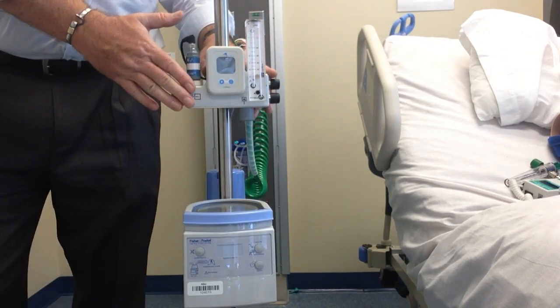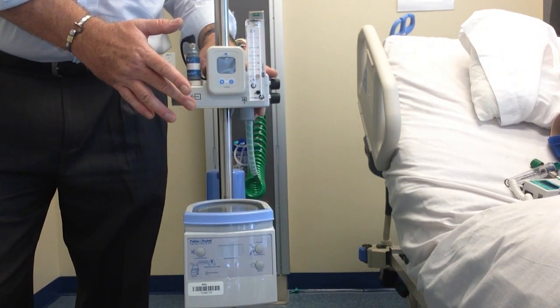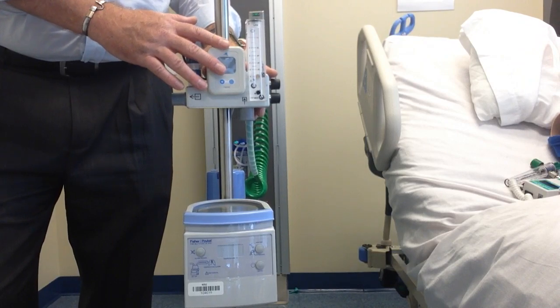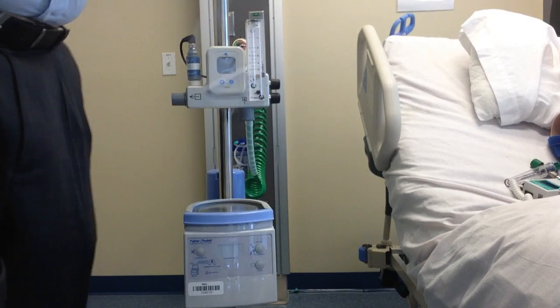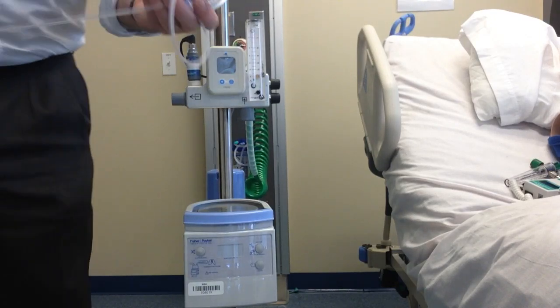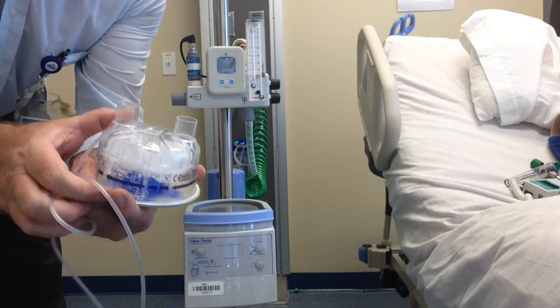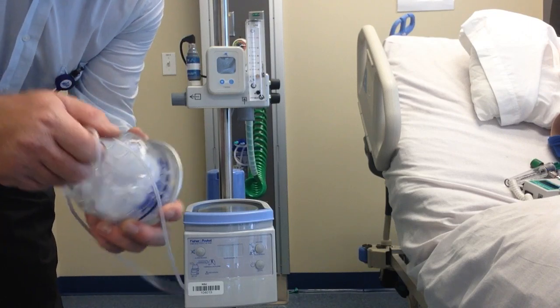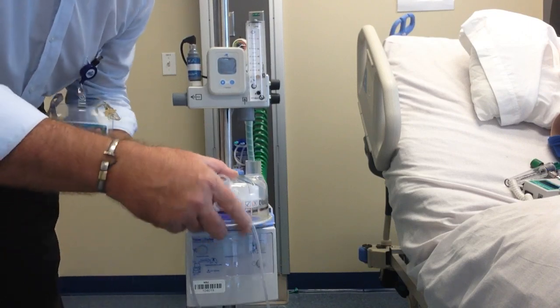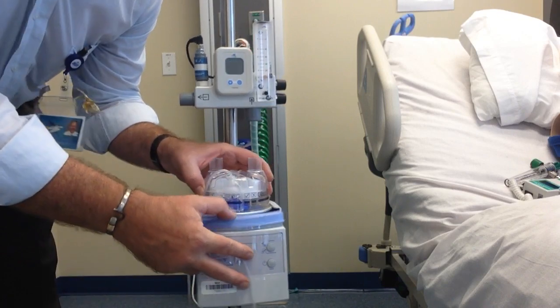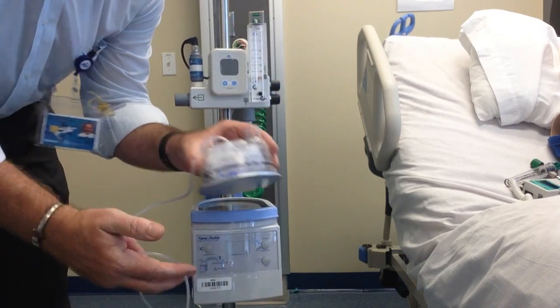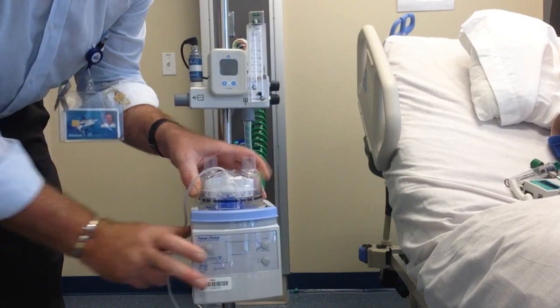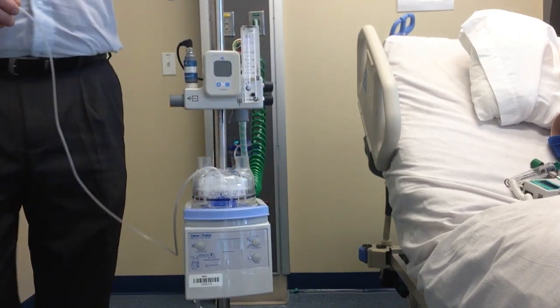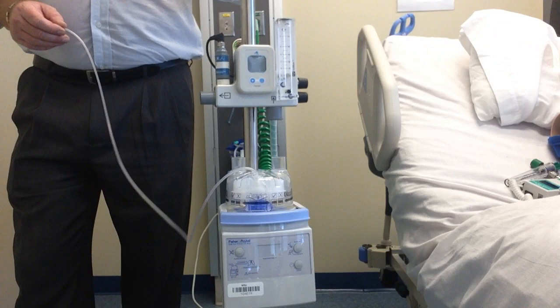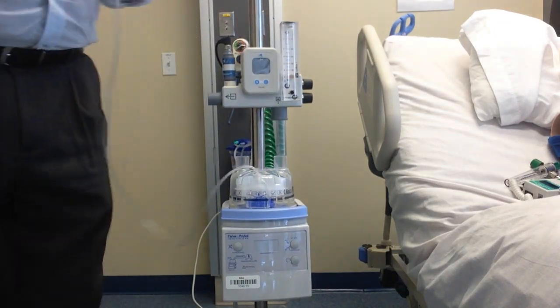We've already gone through the calibration for our oxygen analyzer. So what do we need to do? One, this is the Fisher-Paykel 850 heater. The supply hose, which is on here, this is the heating chamber, will be on a connector. You take that off, pull it off, typically slide that on. This is just a spring load, pushes down, push it down, on. I will go over the full workings of the heater when we get into the humidification systems.